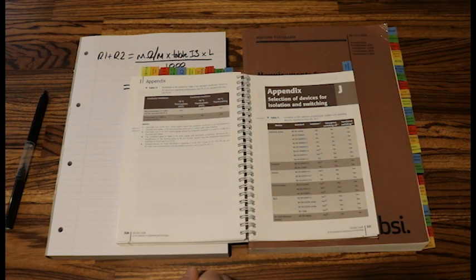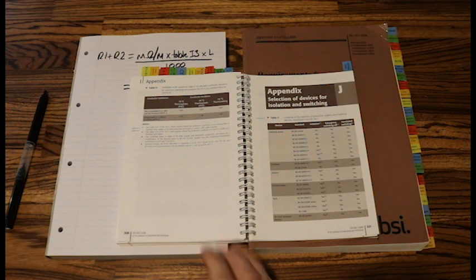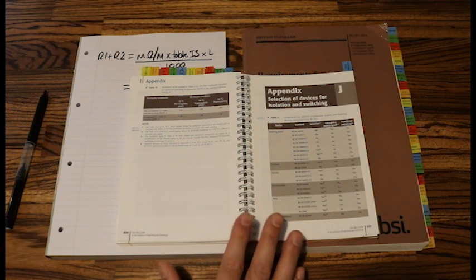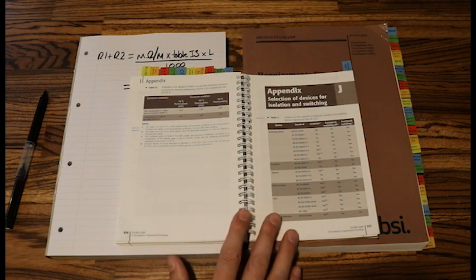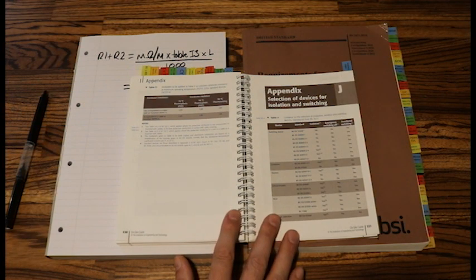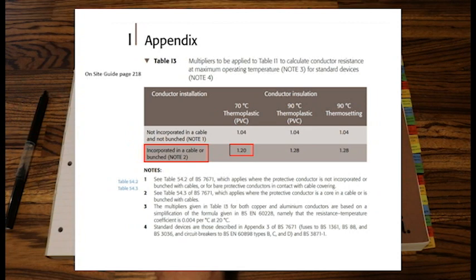If our conductor is incorporated in a cable, that is for any multicore cable. SWA, flex, twin and earth etc. Any multicore cable. So to be honest, the majority of the time for your exam questions, your table I3 multiplier will be 1.2. But it is worth just checking.